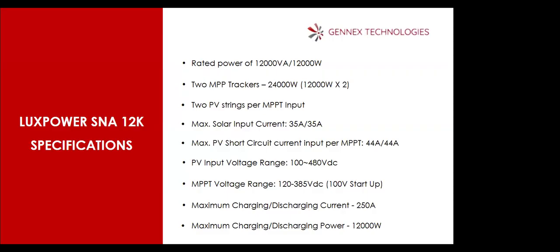So that's why you see 35 amps and 35 amps. That's each MPPT at 35 amps. But the maximum PV short circuit current input per MPPT is 44 amps. That's talking about the short circuit current rating of the panel. Naturally, the panel current should be higher than the current rating of the MPPT itself, where it operates, so that you can capture enough energy. That's just the reason for that. Because when you have a 1,000 watt panel, you cannot always get 1,000 watts from it. So that's the reason why they gave that allowance, so that you can accommodate a lot of panels and deliver up to the specified capacity.